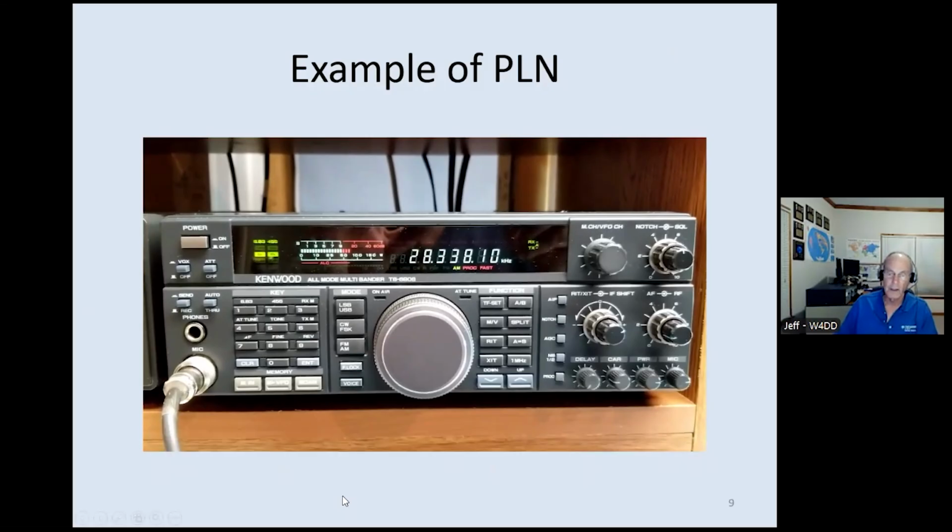Okay. So you listen to it, and it's very even. There's no variation. We hear some sputtering, but there's no, and I call it intelligence in there. Many times in digital transmission, when you have RFI from digital devices, you can kind of say there's some kind of intelligence back there. With PLN, it's very random pulsing.